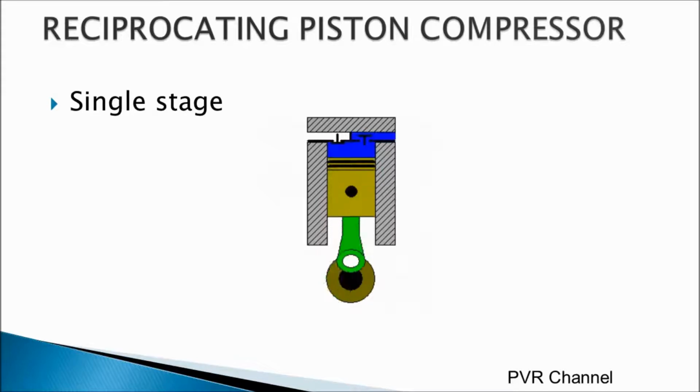So as said earlier, when the piston is moving down, the volume increases, thereby suction is created, and when the piston moves upward, automatically the inlet valve is closed and the outlet valve is open. It works on the principle of Boyle's law. However, there is a drawback in this type of single stage compressor. When the air is compressed above the 6 bar range, the excess heat created greatly reduces the efficiency. Because of this, piston compressors used in industrial compressed air systems are usually of 2 stages.